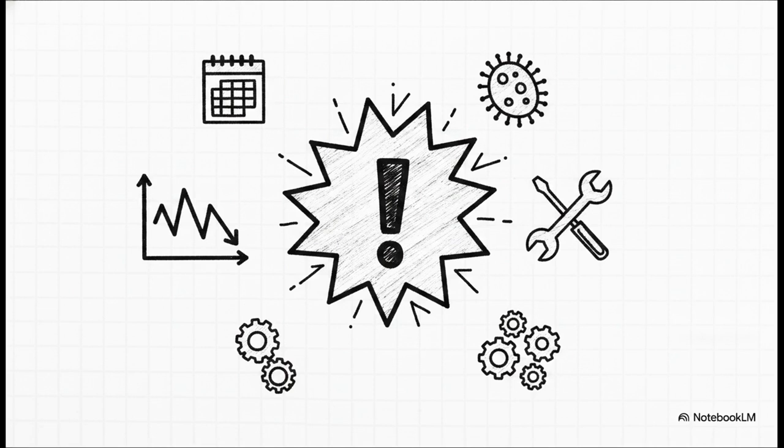If you've had, say, a dozen minor changes that are suddenly adding up, or if your incoming product bioburden unexpectedly shifts, you can not just wait for the calendar to tell you what to do. You requalify right then and there.